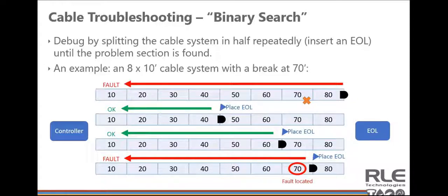So I just want to summarize, this isn't always the most convenient thing. It can be very inconvenient to get underneath a raised floor and troubleshoot this, but it does help. It's something to keep in mind. Just for example, here, instead of testing every section of cable, we're able to find the problem in 3 steps. This is also useful because you can use it in other troubleshooting, like troubleshooting an RS-485 system.